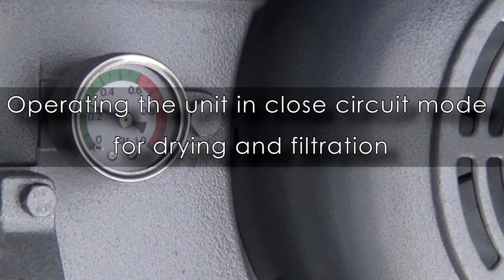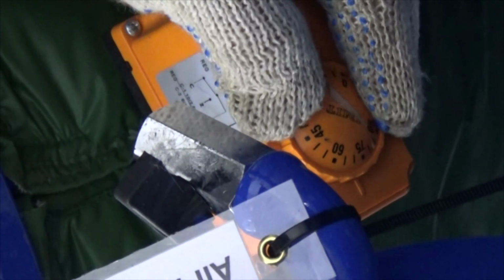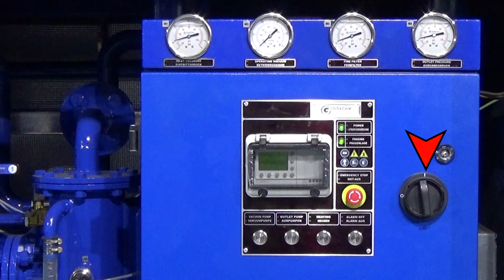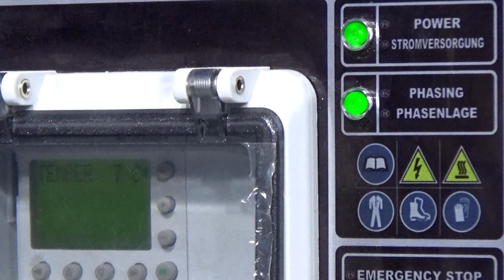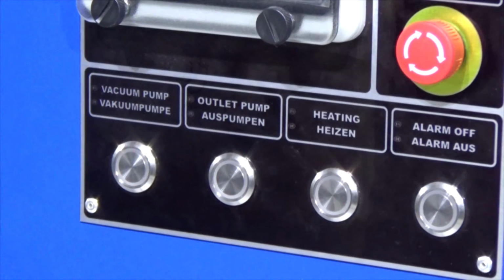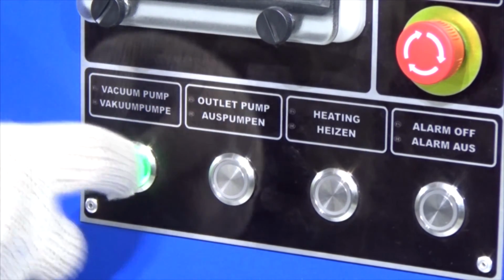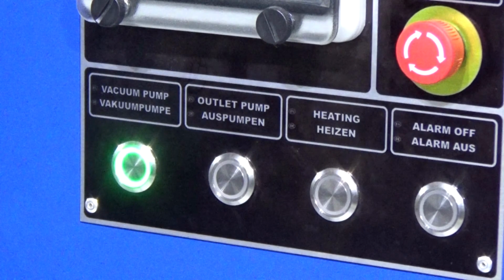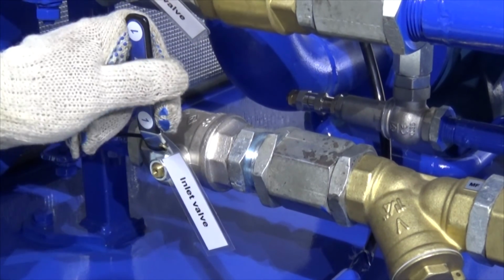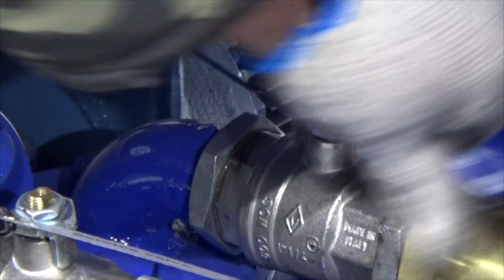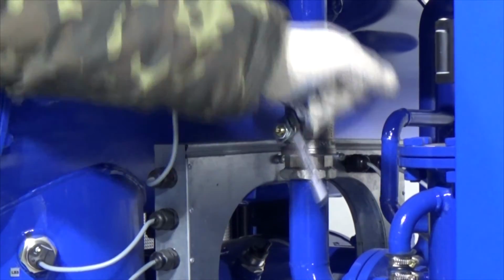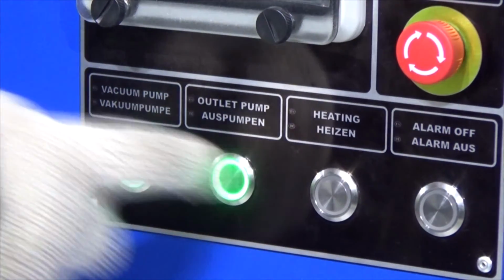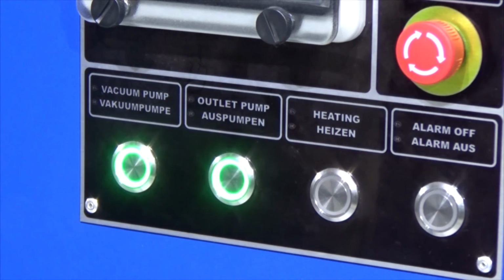Operating the unit in closed circuit mode for drying and filtration. 1. Set the thermostat to the 70 degrees Celsius mark. 2. Power the unit by turning the power handle to the on position. Power and phasing lights must be on. 3. Start the vacuum pump by pressing the vacuum pump button. 4. Open valves MV1, MV4, and MV5. The unit will start to fill with oil. 5. Start the output pump by pressing the outlet pump button. 6. Engage the heater by pressing the heating button.